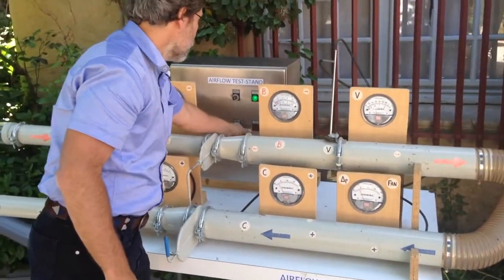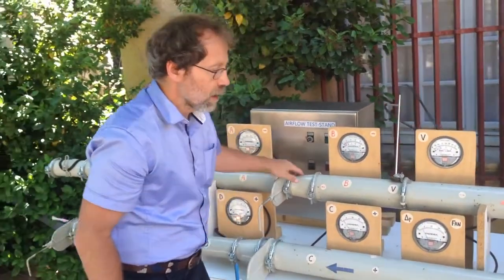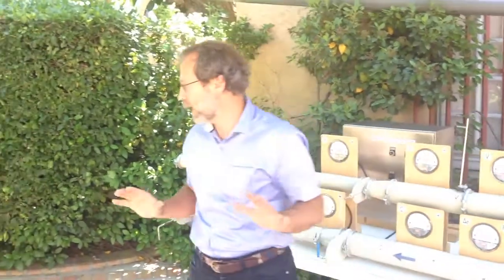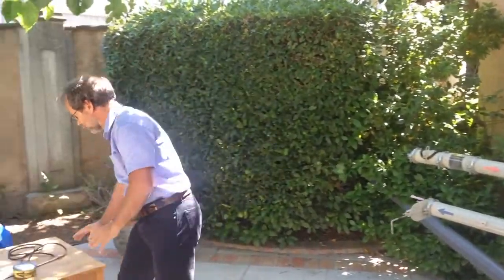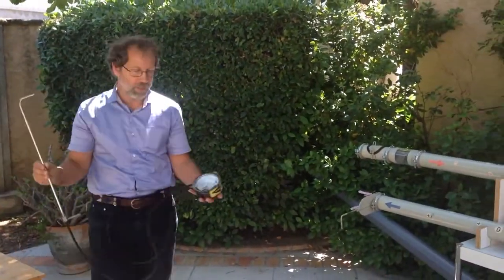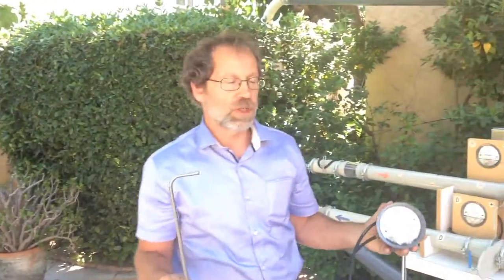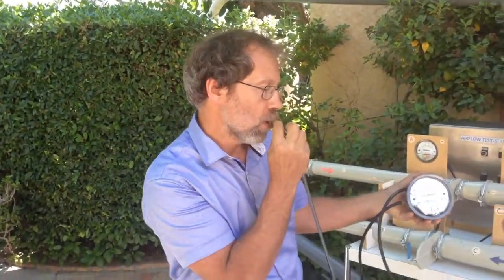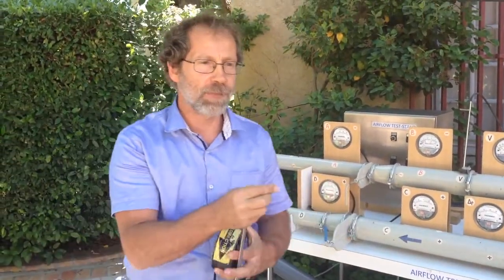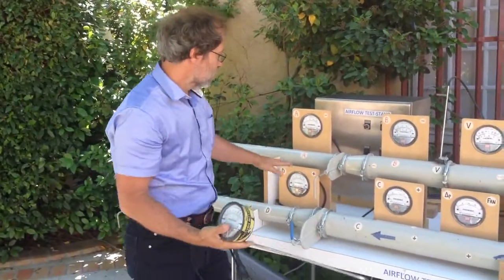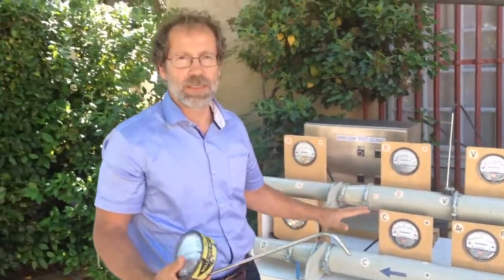Now, let me shut this down. In summary, what I want to say, and that's the true power: if I have a pitot tube which will tell me the airspeed in a duct system, and if I have some gauges which are telling me the static pressure inside a duct system, I will be able to identify any kind of back pressure, resistance and blockages in a duct system. Once I understand that, that's very powerful.